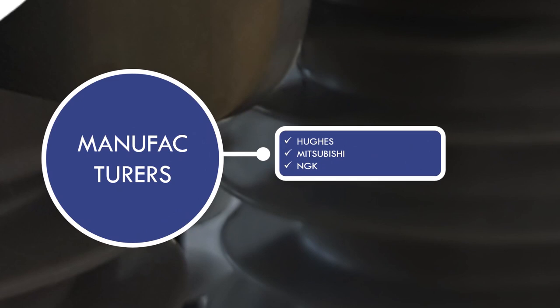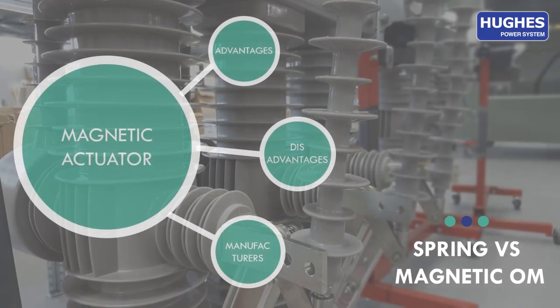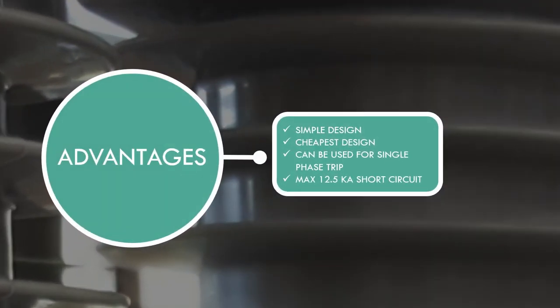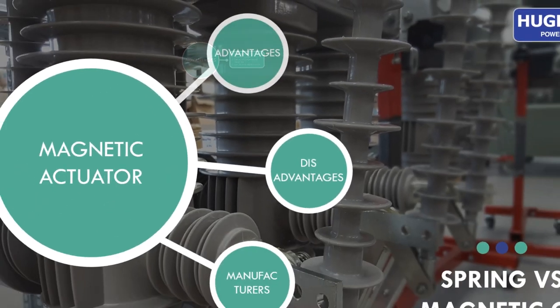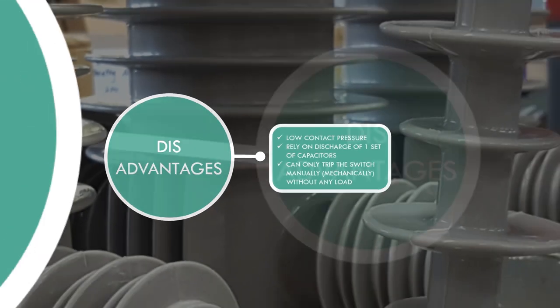Let's have a closer look at the second type of operating mechanism called magnetic. Magnetic type strong point is that it's simple and very cheap design. It can be used for single and triple phase trip and it has maximum 12.5 kA short circuit. The weak point is low contact pressure and risk for contact welding. It relies on discharge of one set of capacitors and it can only trip the switch manually without any load.